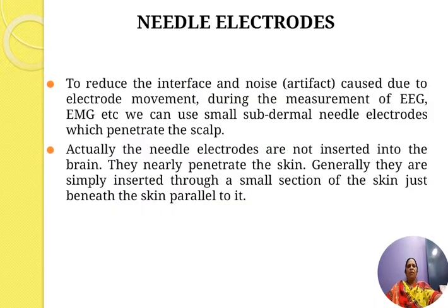Then we have needle electrodes. To reduce the interference and noise artifacts caused by electrode movement during the measurement of EEG, EMG, etc., we can use small subdermal needle electrodes which penetrate the skin. Actually, the needle electrodes are not inserted into the brain. They nearly penetrate the skin. Generally, they are simply inserted through a small section of the skin, just beneath the skin, parallel to it.